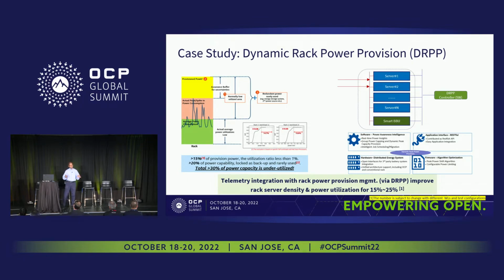So overall data center utilization goes up, and therefore your sustainability numbers go up. Because the measure of sustainability, unfortunately, even today is PUE, power usage effectiveness, which is how much went to IT power versus how much didn't. Here, you're improving that ratio by reducing the power that you provision but nobody used.